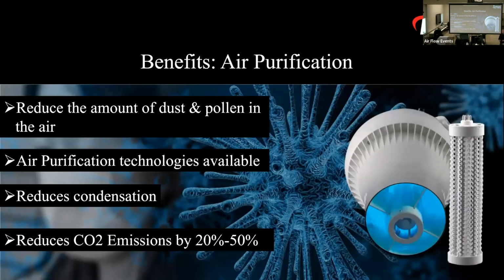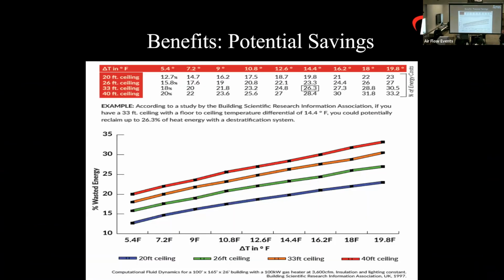Actually, if you go back one slide, sorry. The delta T between the ceiling and the floor on a 33-foot ceiling, I would expect to be higher than 14.4. So this could actually be a little bit understated. Yeah, we're a little bit conservative on it, just to be on the safe side. Usually think a degree a foot. So, 33 feet out of the occupied zone should get 23 degrees, not 14. So yeah, this is conservative, it seems like to me. Yeah, it could be a little bit higher. They did that on purpose, just to be a little bit conservative, because it's always nice if it ends up being a little bit higher than what you expected. So that type of thing.